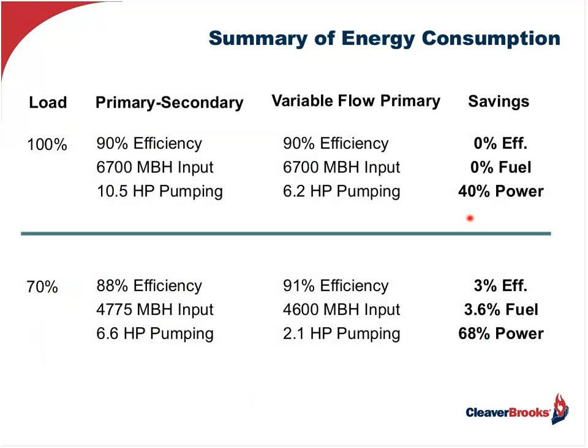The next 2 slides are just a quick comparison. At full load, theoretically, there is no savings. Again, I say this is at full load because typically your system and your boilers aren't going to match, and you're always going to get some mixing, and you will get a savings. Yes, you will get pumping savings, however.